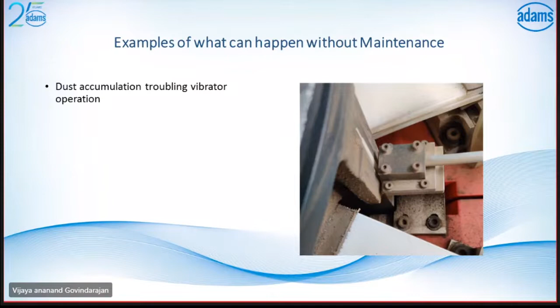If dust accumulates on the reflective sticker or on the sensor, that may give erratic movement of the armature, which may result in incorrect center positioning. That may cause problems to the vibrator. How it will cause that can be seen in the next slide. The flexures will get damaged first. So it will not vibrate about the exact mean position. It may vibrate at a point above or below the mean position. Over a period of time, these flexures tend to bend or deform.